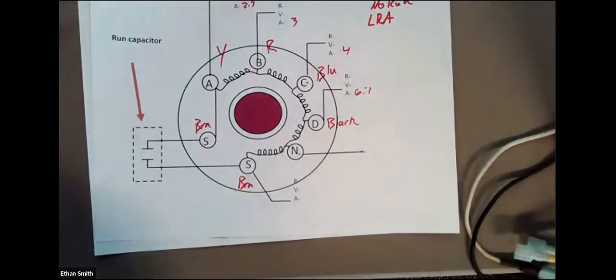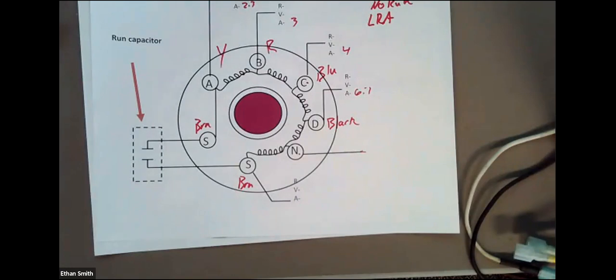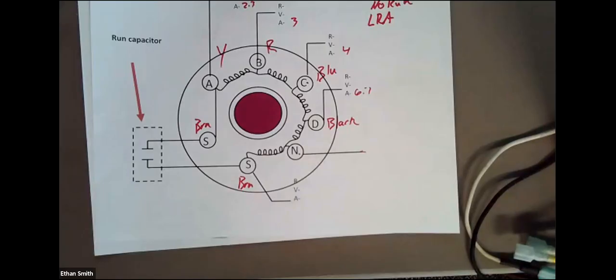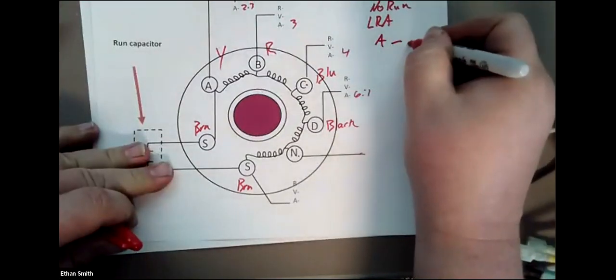I don't think it would run. Or start smoking. I think that falls into the nothing good. I would vote for the possibility of a locked rotor, but it may spin, but it's going to overheat. Locked rotor amperages. So who thinks that the amperage is going to go up versus down? I think it's going to go up. Anyone else? Brandon says it's going to go up. Anybody for down? All right, no votes for down. So it's universally agreed that the amperage is going to go up.